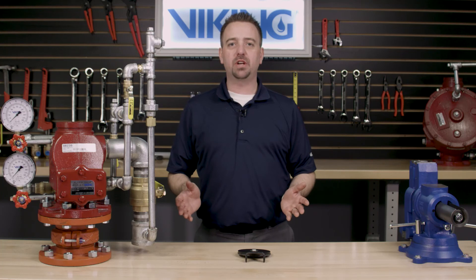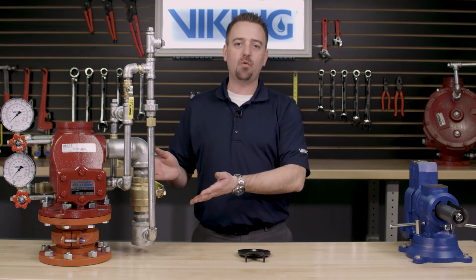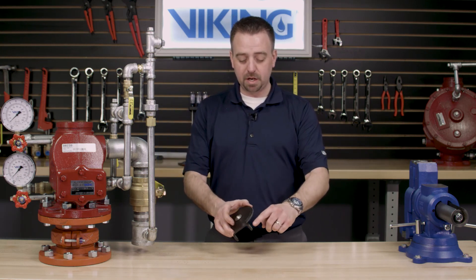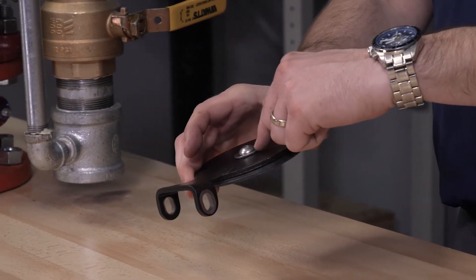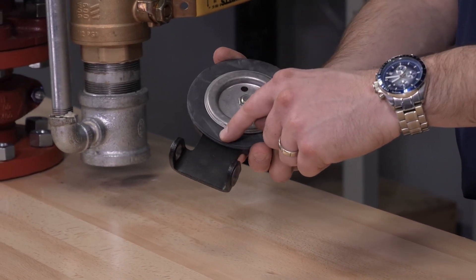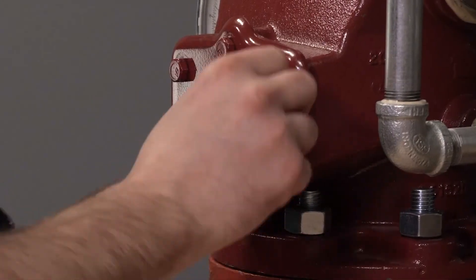Today we will be covering the replacement of the clapper assembly in the Viking J1 alarm check valve. The clapper assembly consists of the clapper, the bushings, the button head screw, the sealing washer assembly, the clapper rubber, the clapper rubber retainer, and the hex nut. We will first need to remove the cover from the valve of the J1 alarm check valve.